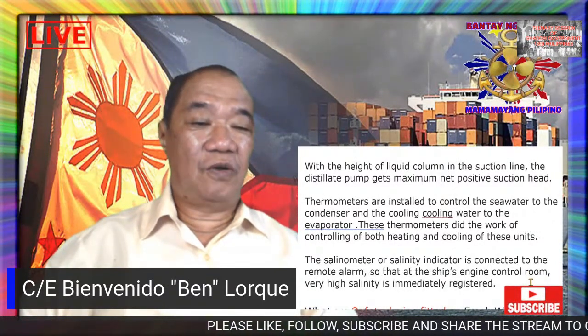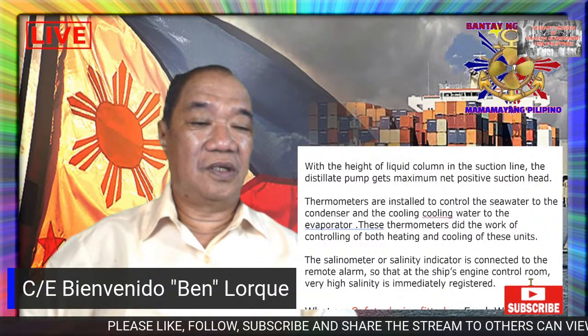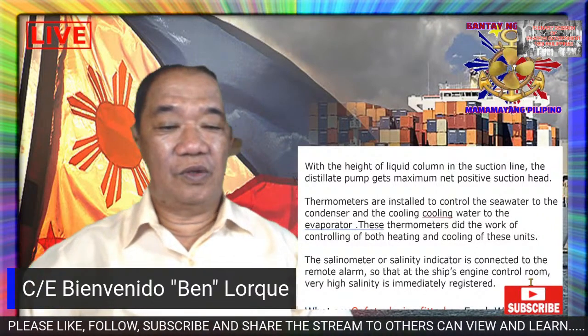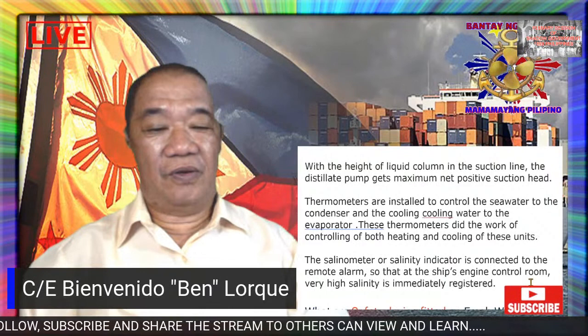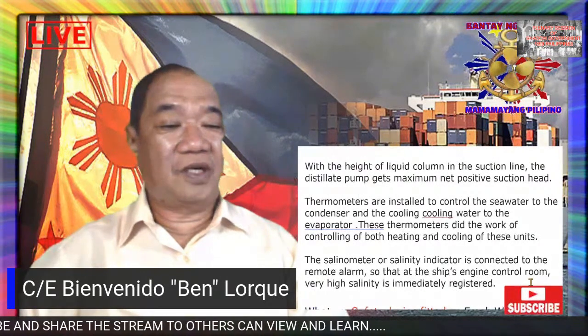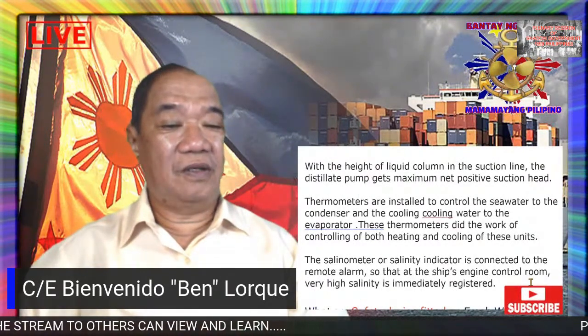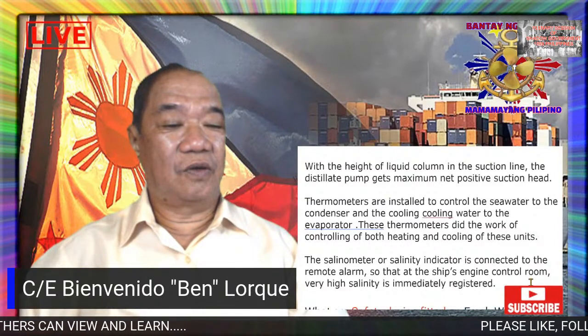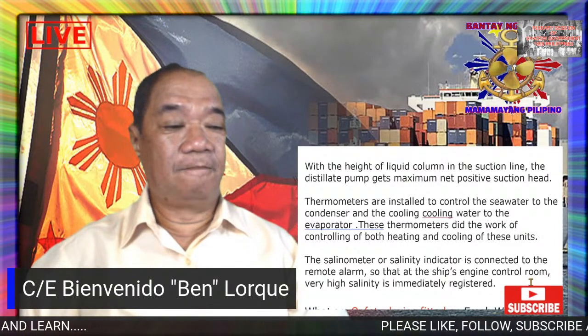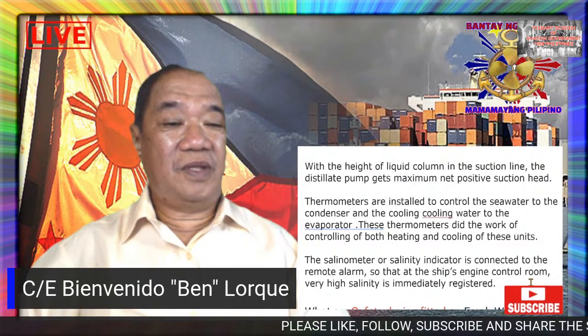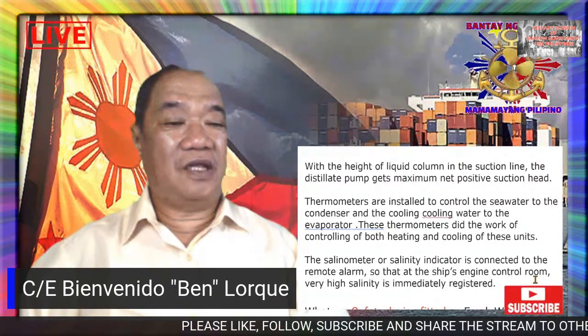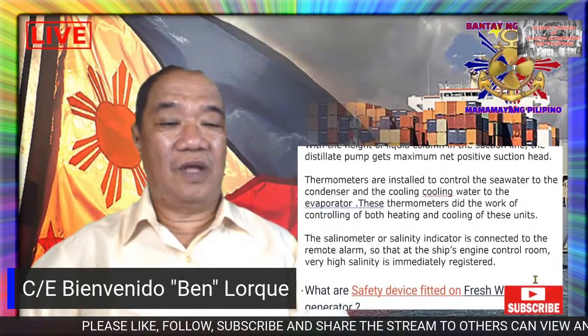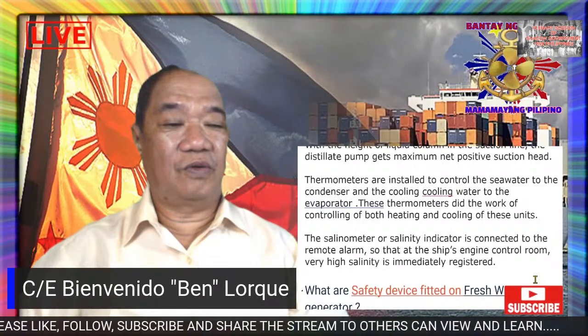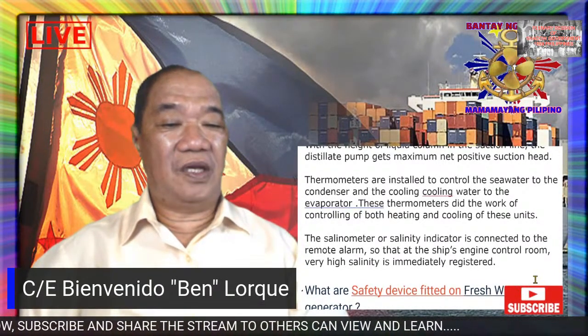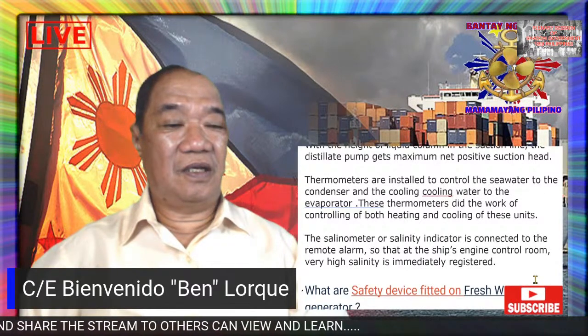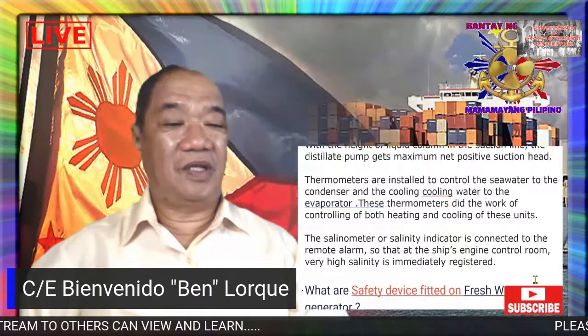Thermometers are installed to control the seawater to the condenser and the cooling water to the evaporator. These thermometers do the work of controlling both heating and cooling of this unit. The salinometer, or salinity indicator, is connected to a remote alarm in the ship's engine control room so that very high salinity is immediately registered.